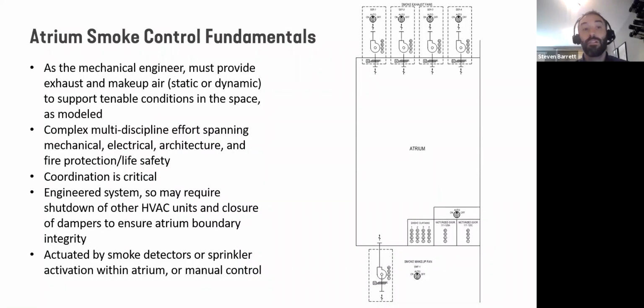So as the mechanical engineer, you need to provide exhaust and makeup air. And the makeup air could be active or passive to support these tenable conditions in the space. And this can be really complex. It requires a lot of disciplines across the whole board to establish a system that actually does work and meets all of the stakeholders' intents. So it's critical to coordinate with all these multiple disciplines.